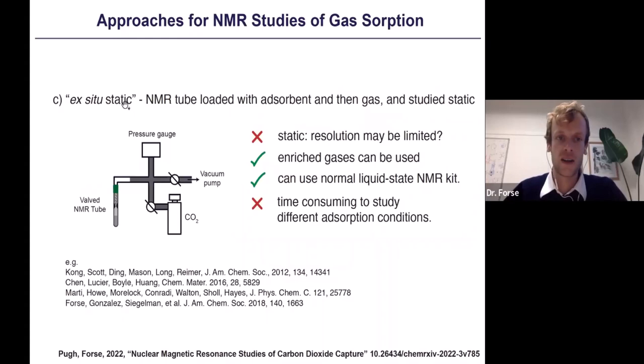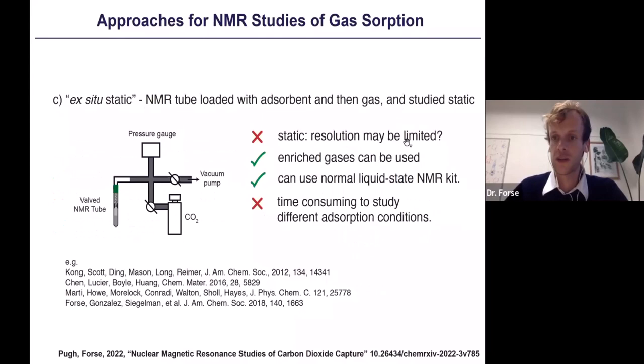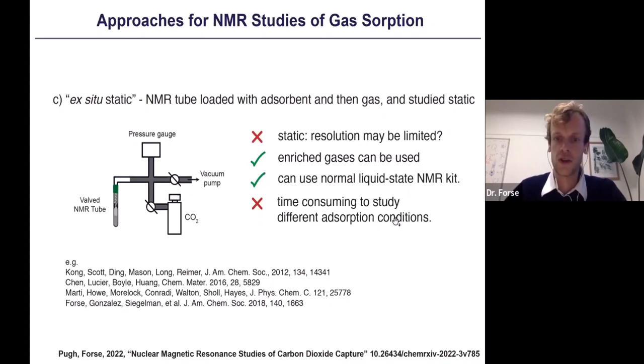Ex situ static has many similarities to ex situ MAS, except the sample is static. We have a valved tube where the adsorbent is dosed with gas, then the tap is closed and the tube is taken to a solution-state NMR spectrometer. A potential disadvantage is that resolution may be limited since the sample is static. We can still use enriched gases since the system volume can be kept small. It is time-consuming to study different adsorption conditions since you need to return the sample to the dosing manifold each time.